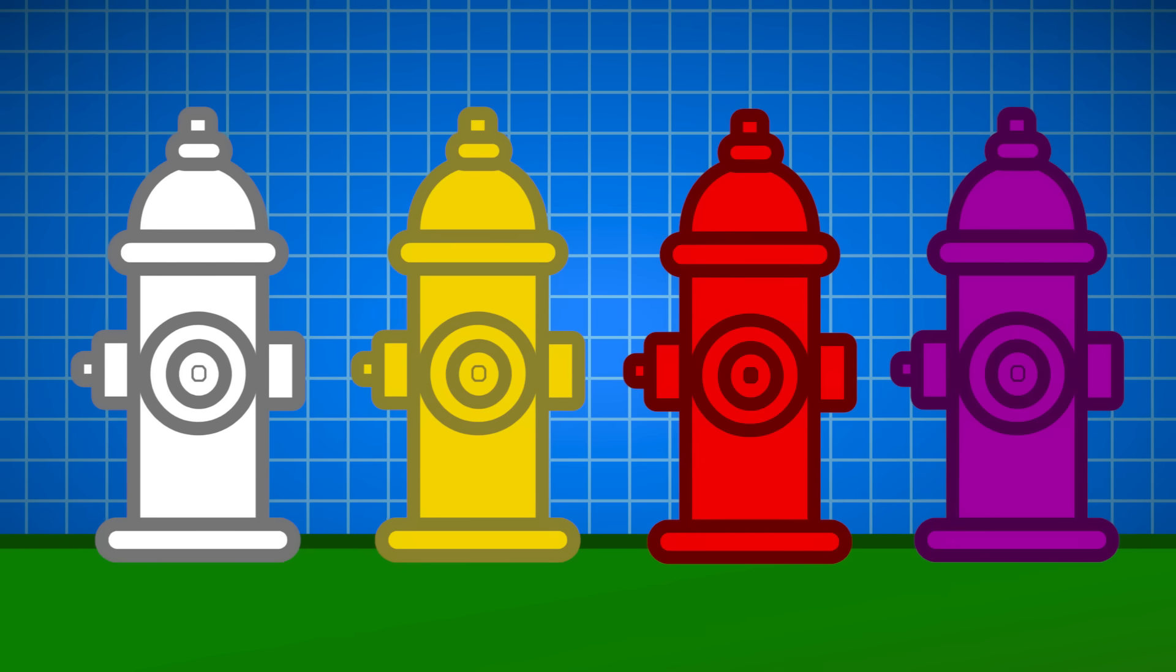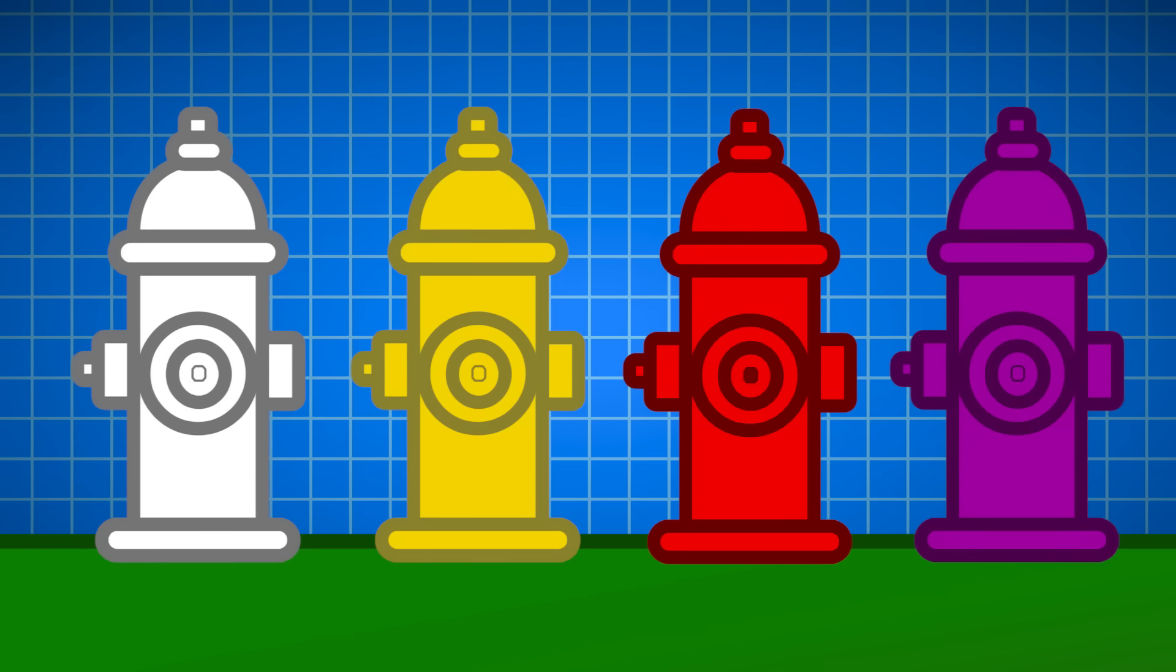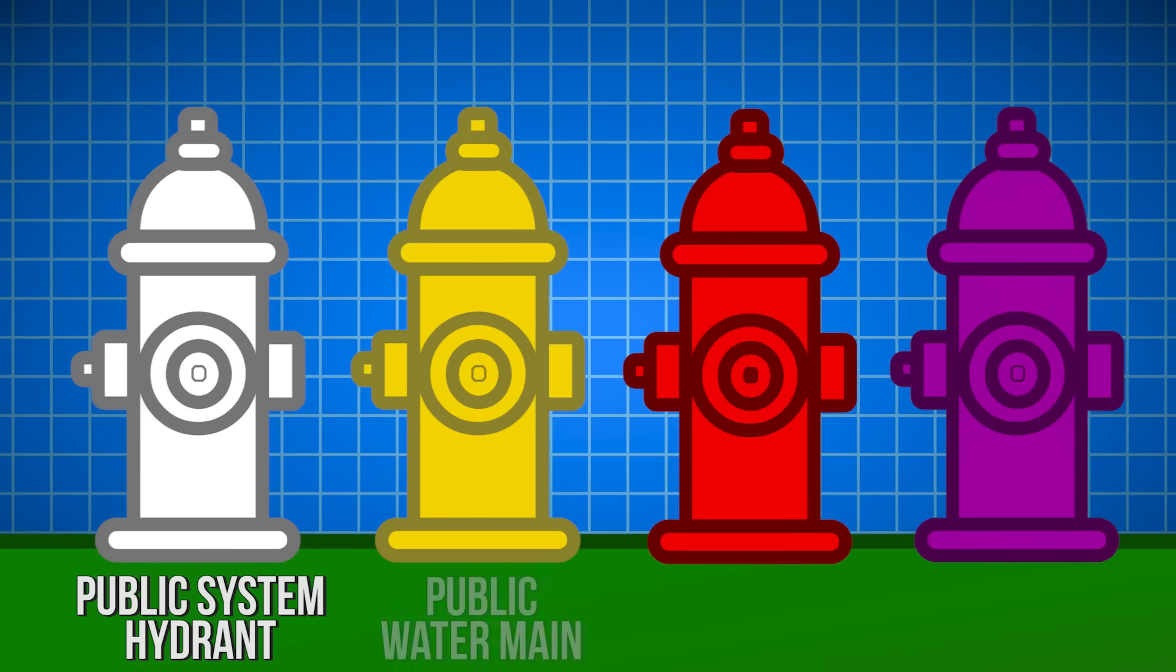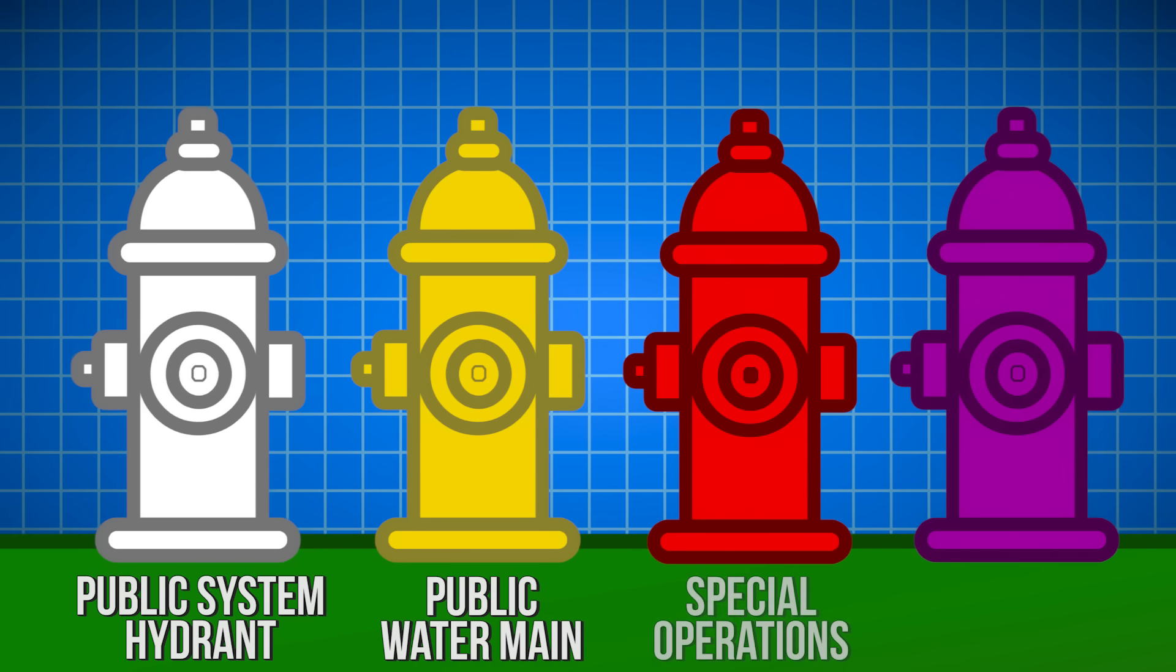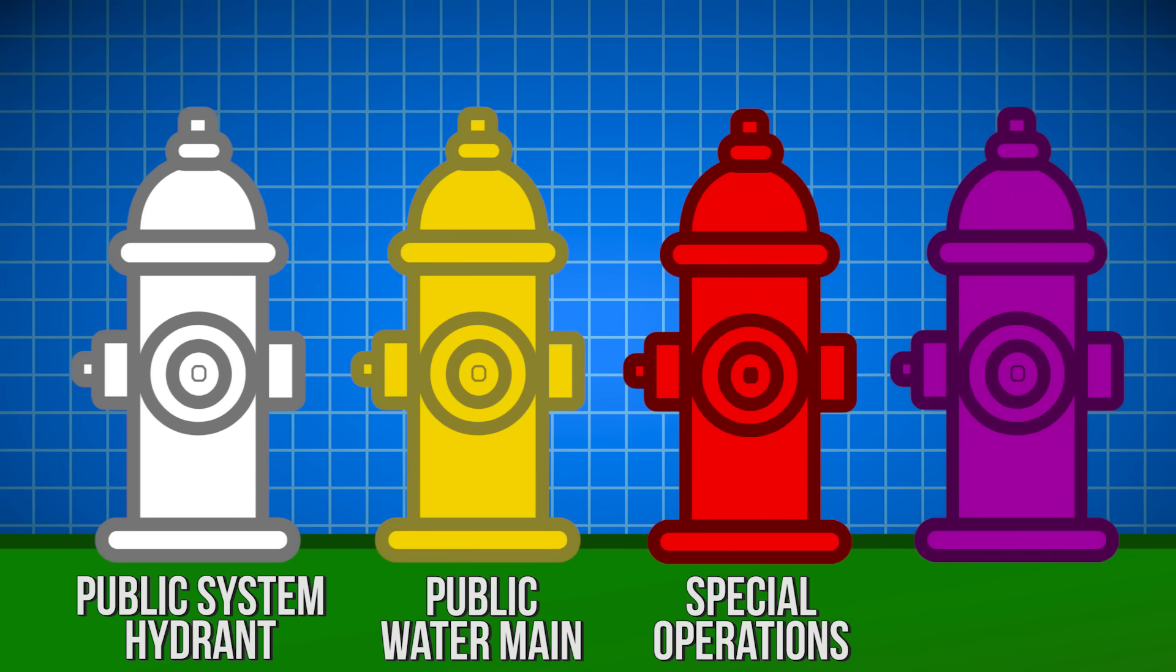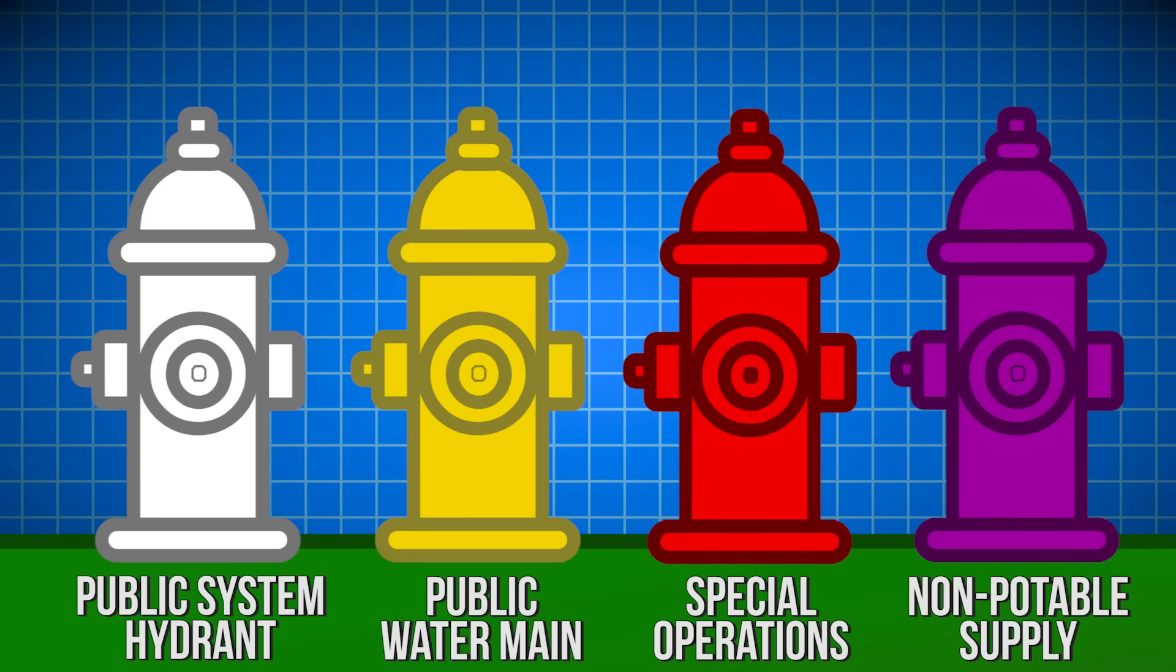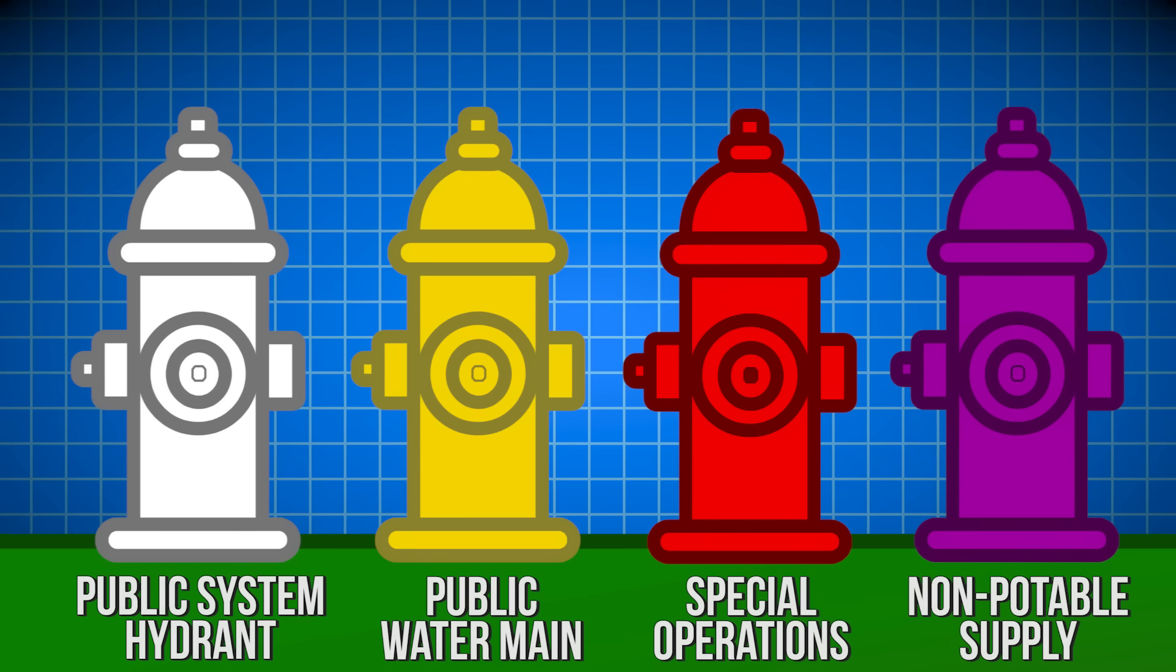In the US, the colors of hydrants can also indicate their type. White means public system hydrant, yellow means it's connected to a public water main, red means it's for use in special operations and not for other use, and violet means non-potable supply, or water from an untreated source like a lake.